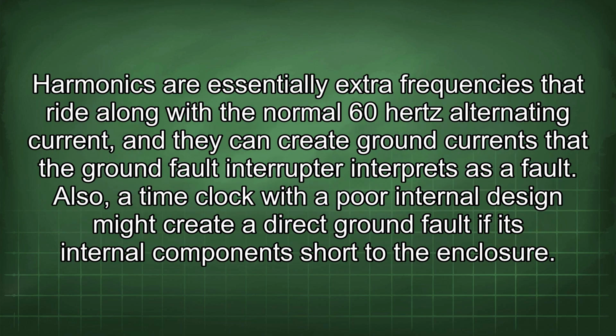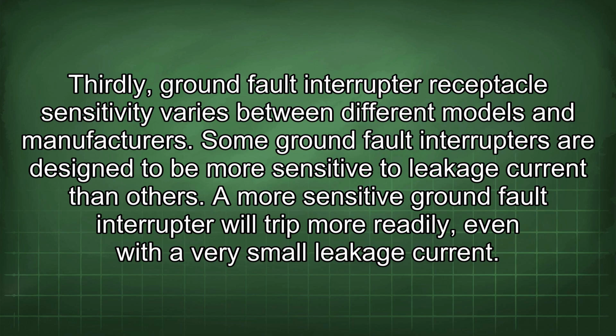Harmonics are essentially extra frequencies that ride along with the normal 60 Hz alternating current, and they can create ground currents that the ground fault interrupter interprets as a fault. Also, a time clock with a poor internal design might create a direct ground fault if its internal components short to the enclosure. Thirdly, ground fault interrupter receptacle sensitivity varies between different models and manufacturers.